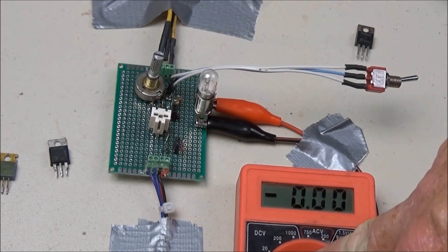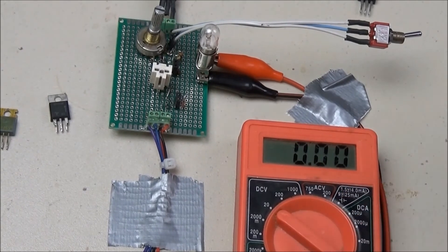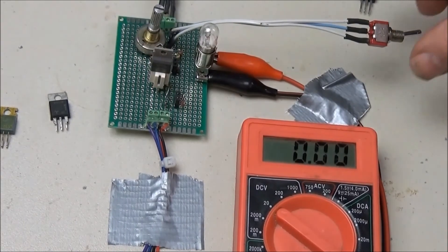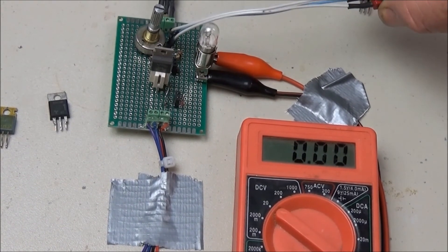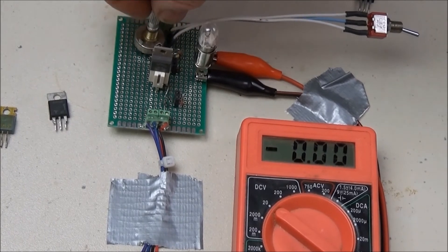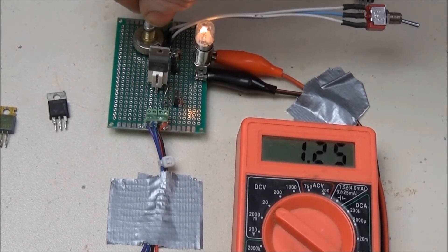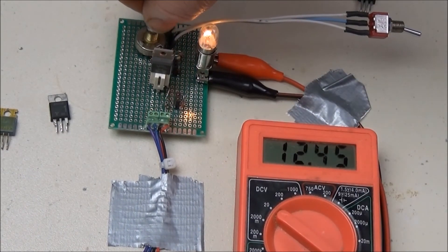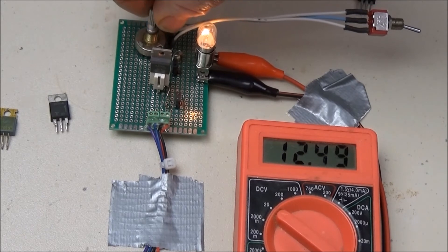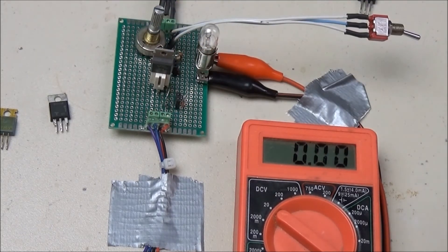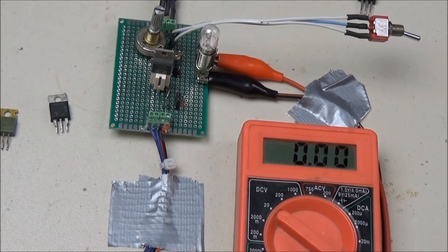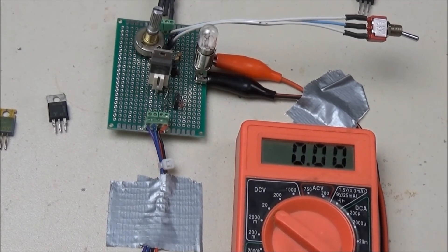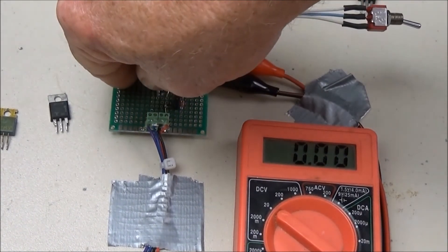The meter is set for DC if you can see that, the power is off. I'm going to plug in an SCR. An SCR when turned on of course acts as a half wave rectifier. So when I trip it on all I'm going to do is get pulsating DC. That is not what I'm supposed to get on a triac. And it also tells me either one side of the triac is blown and that is possible or it's an SCR. I know it's an SCR by the part number.